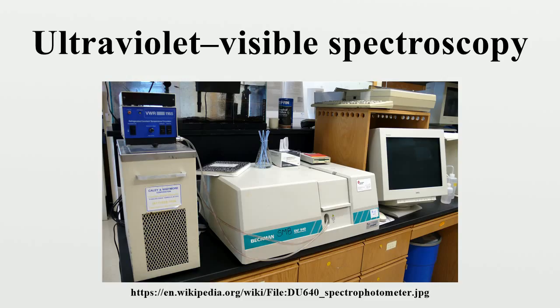The Beer-Lambert law has implicit assumptions that must be met experimentally for it to apply; otherwise there is a possibility of deviations from the law. For instance, the chemical makeup and physical environment of the sample can alter its extinction coefficient. The chemical and physical conditions of a test sample therefore must match reference measurements for conclusions to be valid. Regarding spectral bandwidth, monochromaticity of light incident on the sample cell is the width of the triangle at one-half of the peak intensity. A given spectrometer has a spectral bandwidth that characterizes how monochromatic the light is. It is important to have a monochromatic source of radiation for analysis of the sample. If this bandwidth is comparable to the width of the absorption features, then the measured extinction coefficient will be altered.